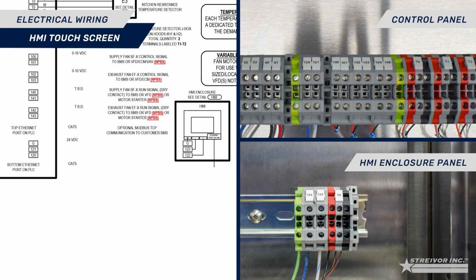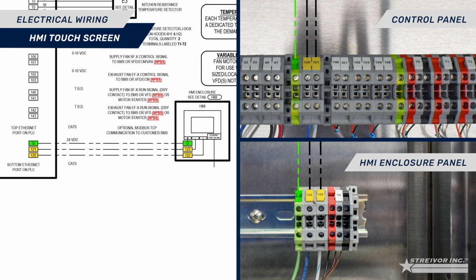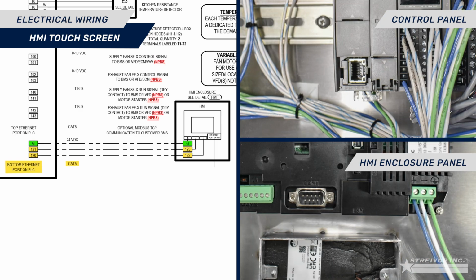To supply power to the HMI touch screen, wire terminal block 121 from the control panel to terminal block 123 in the HMI enclosure panel. Wire terminal block 120 from the control panel to terminal block 122 in the HMI enclosure panel. And ground. Connect a Cat5 Ethernet communication cable from the control panel to the Ethernet port on the HMI.